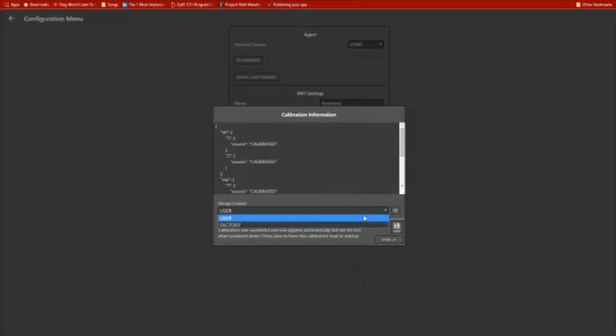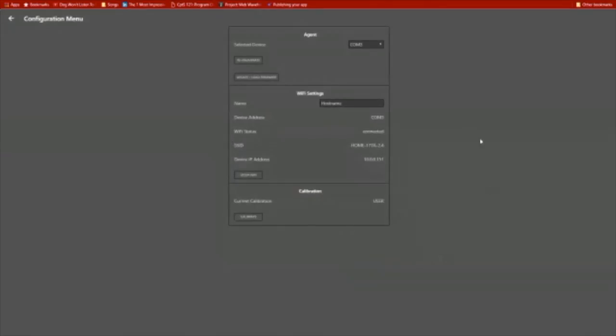So we calibrate it once before we ship it to you, and that's the factory calibration. And then you can save it as a user calibration to use all those offsets when you're actually acquiring data. So he'll go ahead and hit save there. And that's saved on the device itself. So if he unplugs it and takes it to work and uses it there, that calibration information is still saved in the device itself. Then if he hits done, the other thing we'll look at here is the Wi-Fi settings.